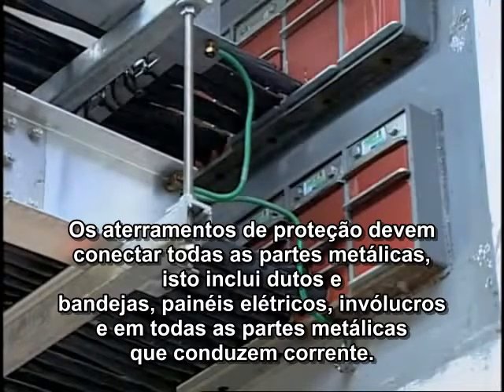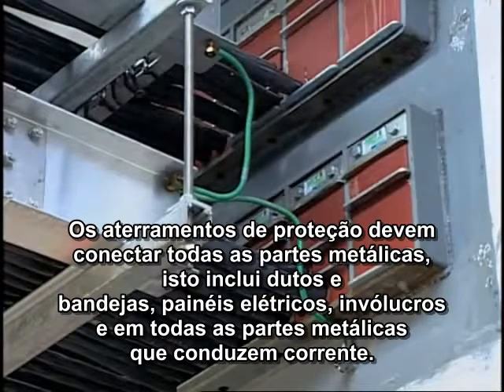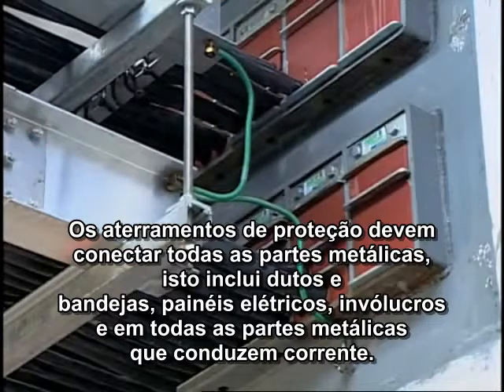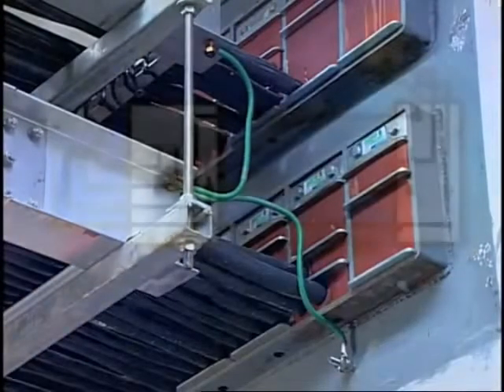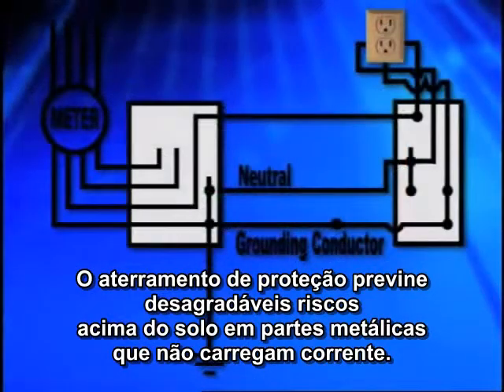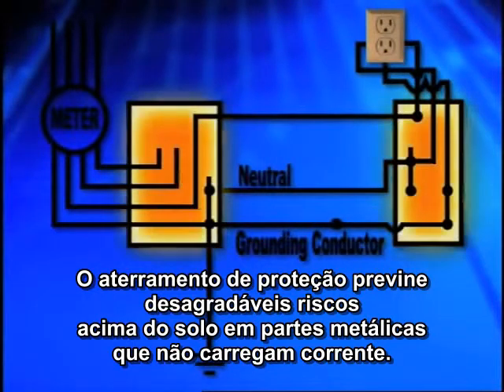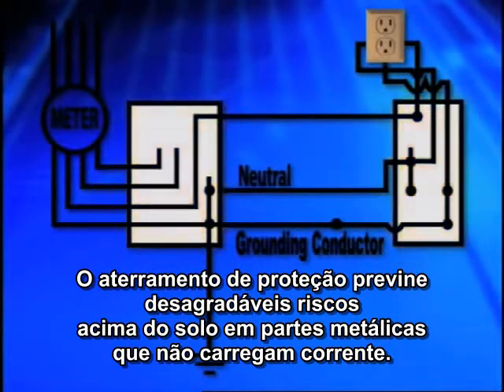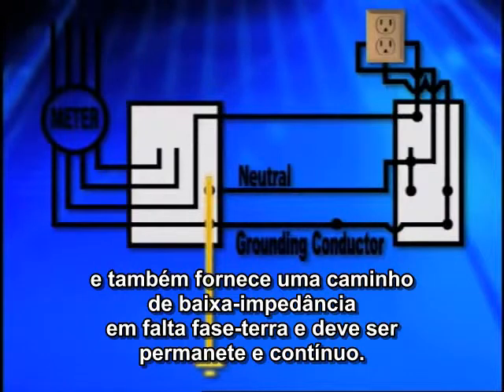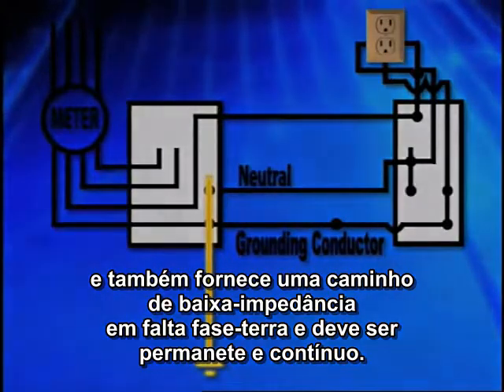Equipment grounds bond together all the metal parts of a conductor path. This includes electrical raceways, boxes, and enclosures on all non-current carrying metal parts. Equipment grounds prevent objectionable potential above ground on non-current carrying metal parts. It also provides a low impedance path for ground faults and must be permanent and continuous.